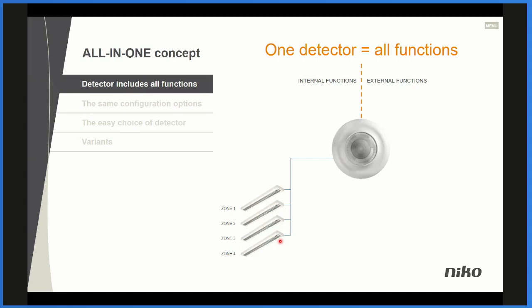Within the detector, there's a built-in potential-free relay, and this relay has a lot of options. It could be that we have non-dimmable DALI luminaires that have to be controlled. That means we can choose them for controlling the light on or off. It could also be an integration of the HVAC system or the ventilation system.